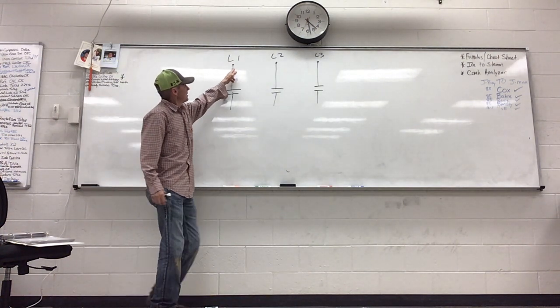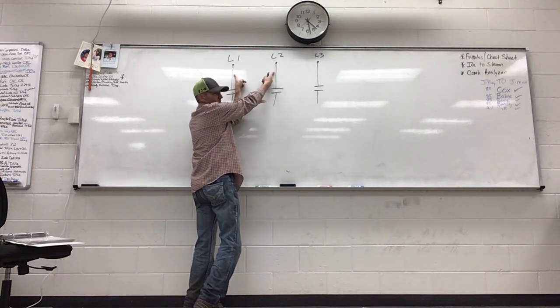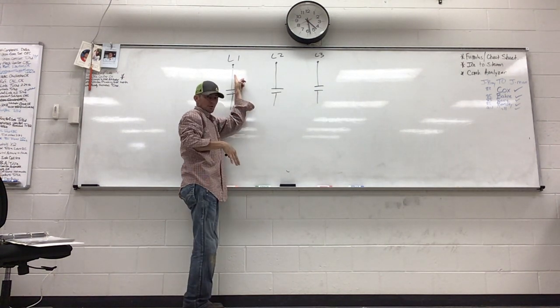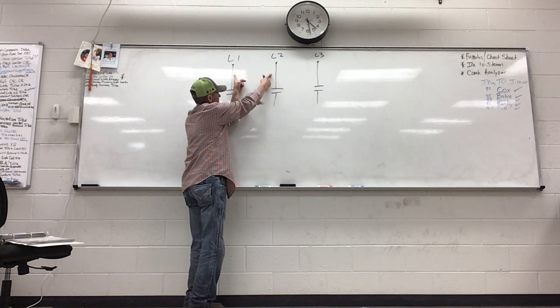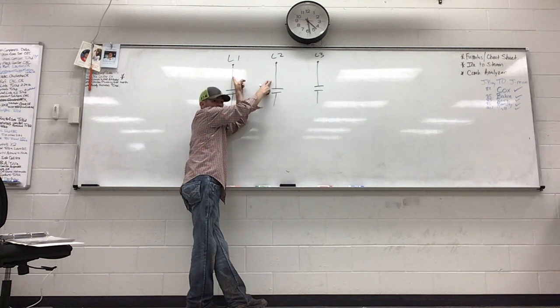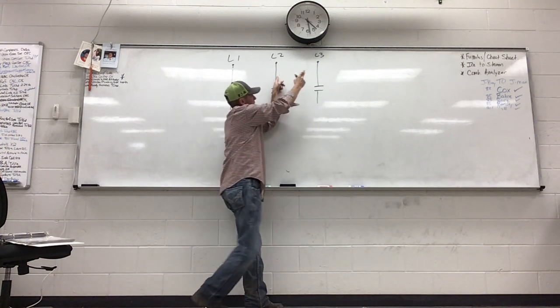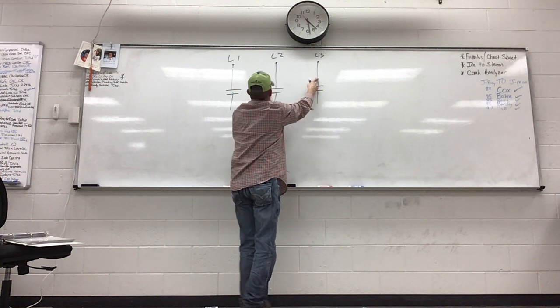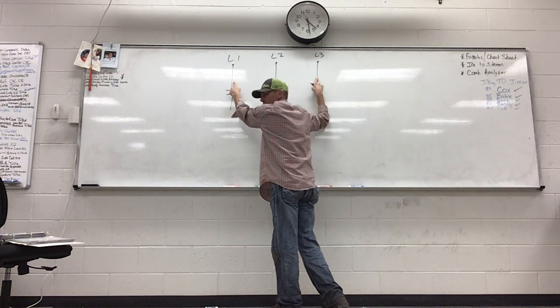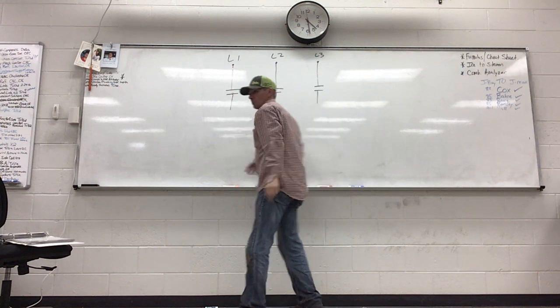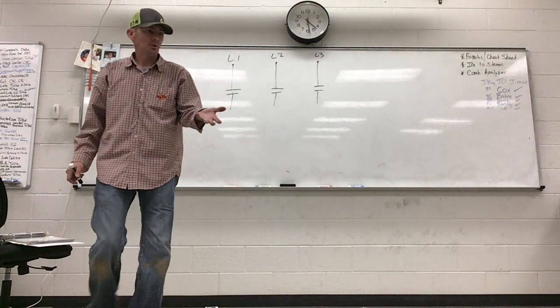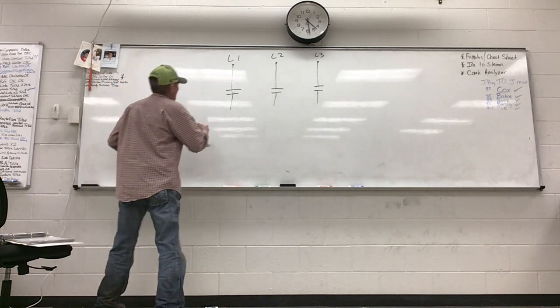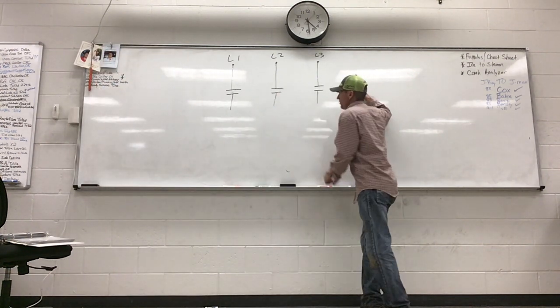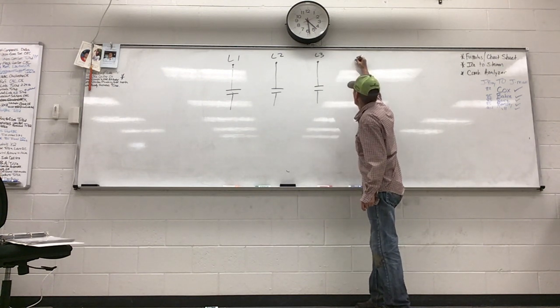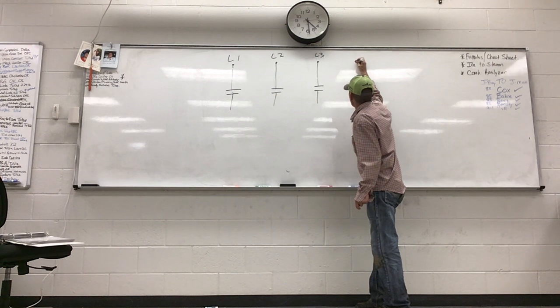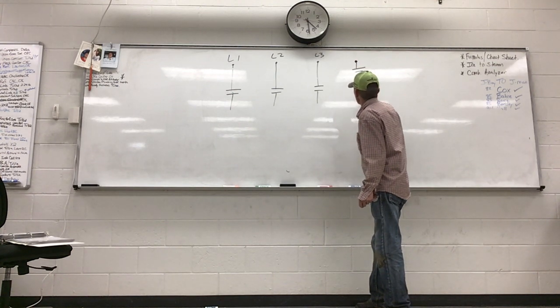When I go from L1 to L2, I have a potential difference. I'm going to read the full potential, right? So if it's in our building here, between L1 and L2, line 1, line 2, I should read 208, right? And from 2 to 3, I should read 208. And from 1 to 3, I should read 208. No matter which leg, no matter where I go, there should be a potential difference of our full applied voltage, right? Okay, so I'm going to do something else right here. I'm going to put a ground screw. Let's say we're in a disconnect or we're in a package unit, a rooftop unit, whatever. And so I'm going to add a ground screw right here, or a ground whatever. There's a ground.